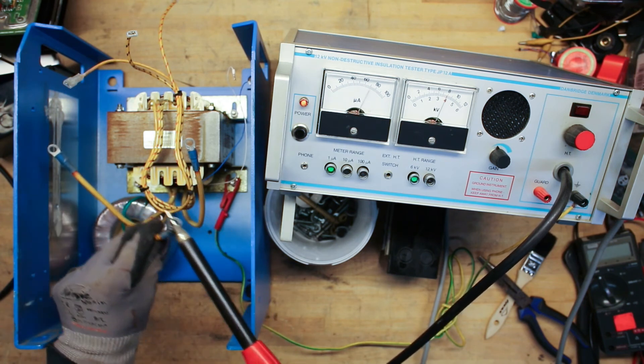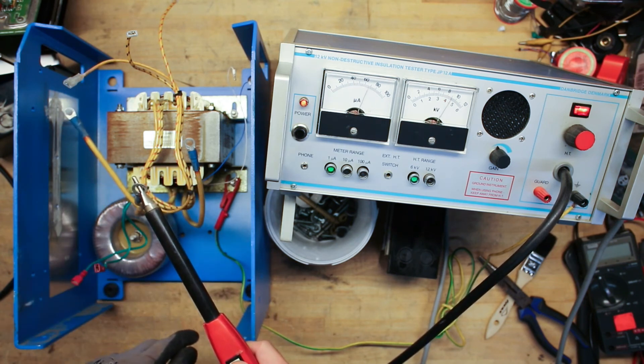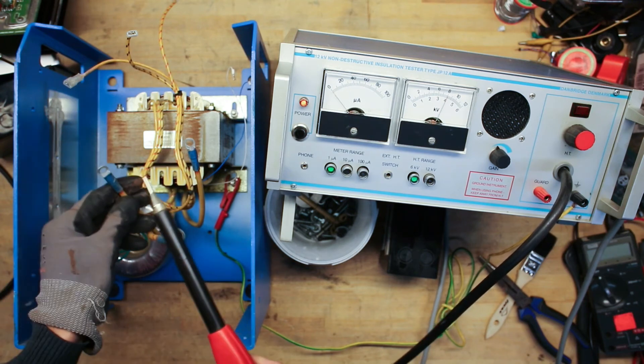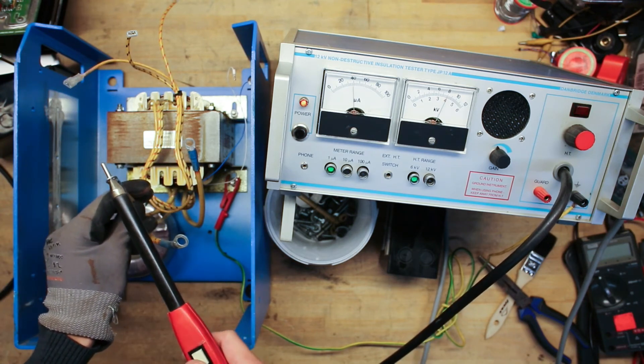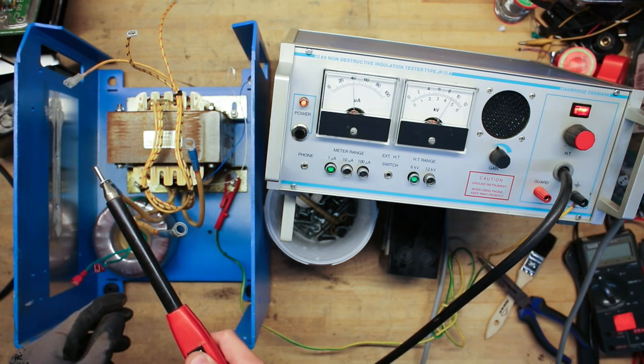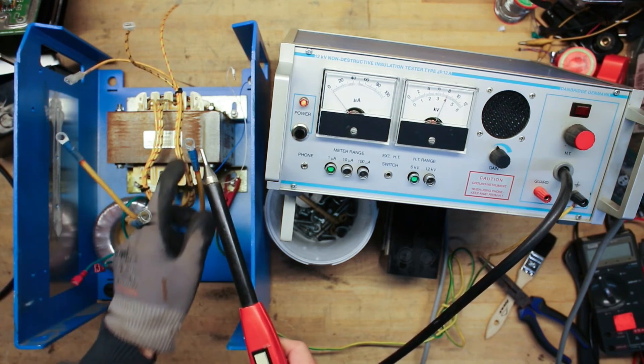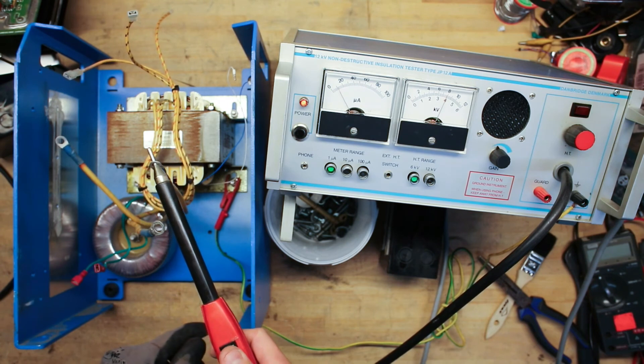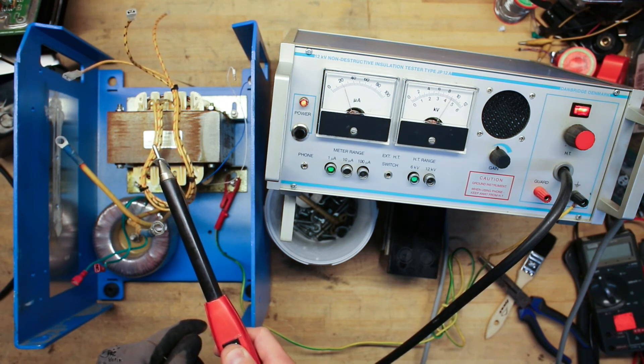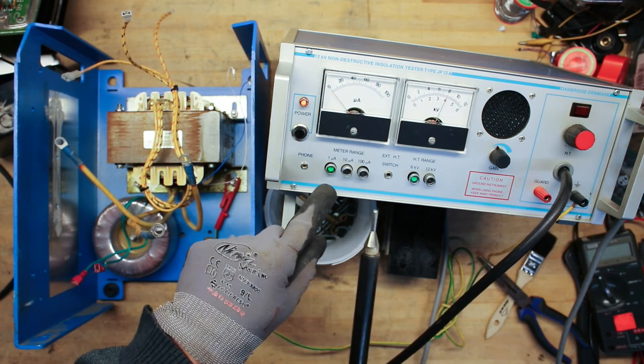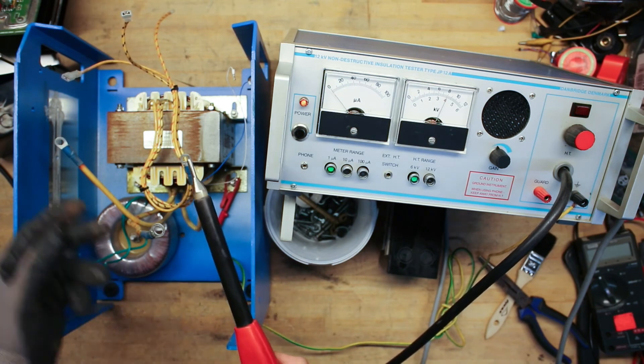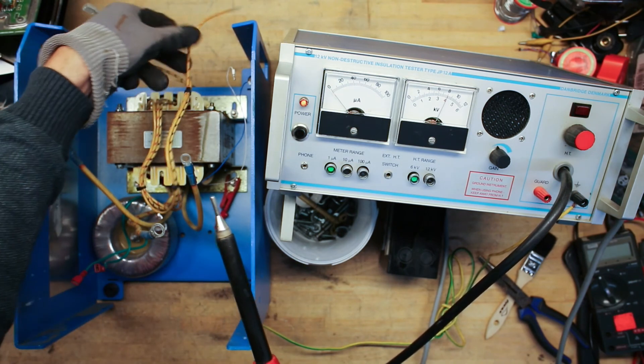So we are looking for some kind of leakage to ground. Let's start off with the secondary side. As we activate the high potential. Which is set for 6kV. Then we should see no extremely high currents being drawn. As we can see it's set for the lowest range. One micro amp.